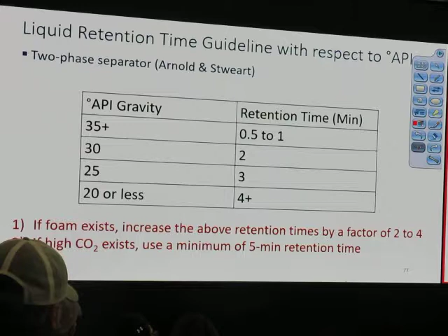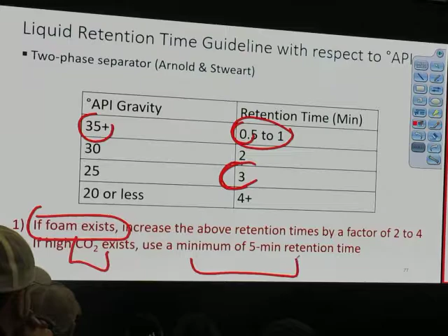Oh, we have 40 degree API. Okay, 40 degree API, how much retention time do I need for liquid phase? I go back to that. Okay, maybe 1 minute, 2 minutes may be fine. 3 minutes will be, even if we have foam, if we have like 0.5 multiplied by 4, 3 minutes will take care of it for sure, right? At least 30 seconds, okay? If we have CO2, we do minimum of 5 minutes. So this is how we know the retention time.